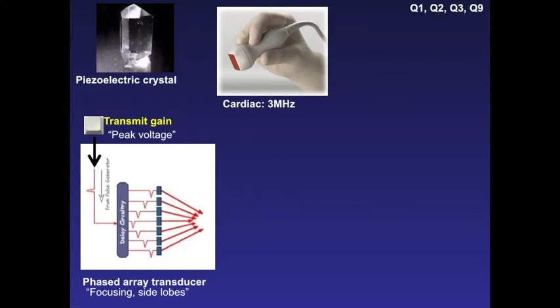The probes themselves have been designed with a frequency and a shape in mind, so that, for instance, the cardiac probe is set so you can get intercostal between the ribs. The abdominal probe, which is a higher frequency, the crystals are aligned in this curvilinear pattern so that you can image deep into the belly without having any sharp edges. And then finally, a vascular probe is flattened or linear in its arrangement of crystals, so it can give you a view of flat surface structures, such as vascular images of the carotid or of the veins.